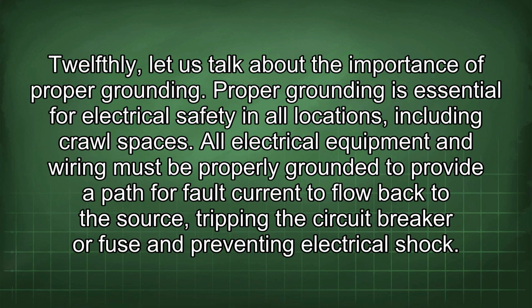12thly, let us talk about the importance of proper grounding. Proper grounding is essential for electrical safety in all locations, including crawl spaces. All electrical equipment and wiring must be properly grounded to provide a path for fault current to flow back to the source, tripping the circuit breaker or fuse and preventing electrical shock.